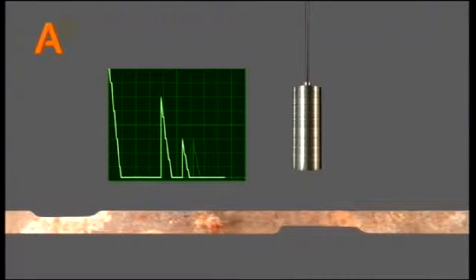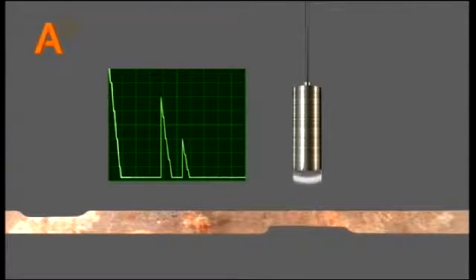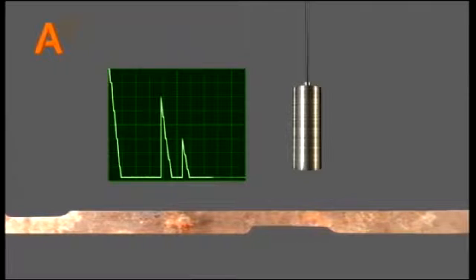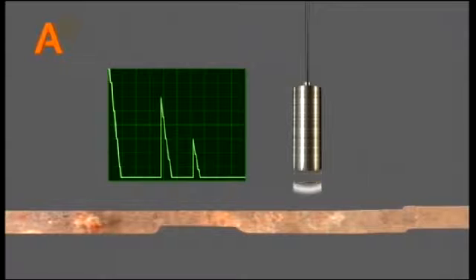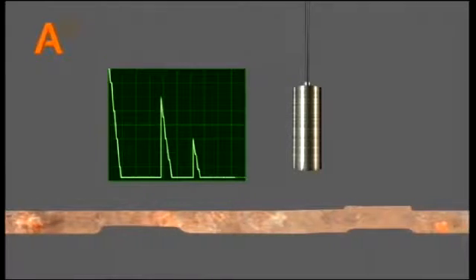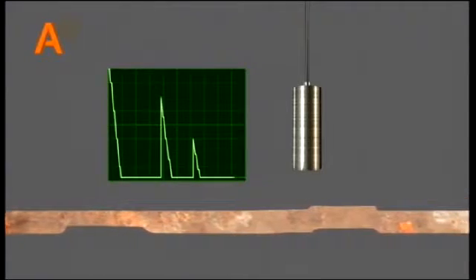A part of the ultrasonic pulse continues in the pipe wall material and is reflected by the pipe outside surface. This can be seen as the second pulse on the screen, providing information about the wall thickness and possible external corrosion.